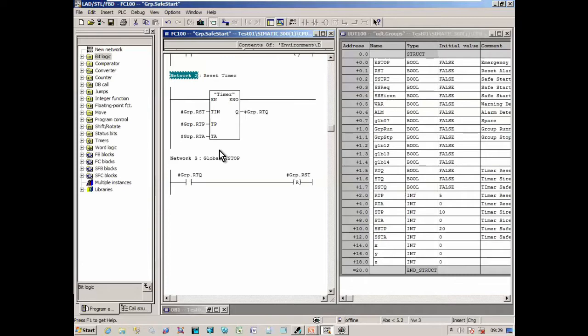The first scan will reset the fault of the latched interlock, and then the second scan will reset the latched fault of something else, and so on until it resets all the faults, the cascade of faults, and then the reset function can reset itself, and we'll have our plant back to a normal state, and we can try and start it again.